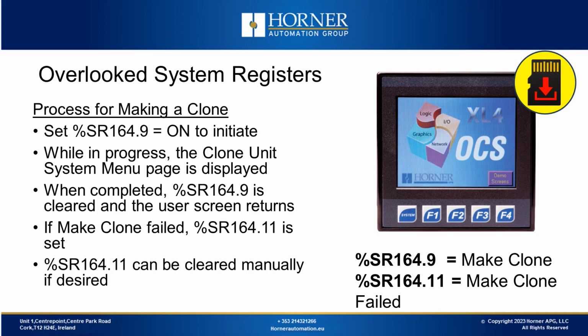We can also monitor another bit, SR164.11, which signals if there's an issue during cloning. If there's a problem, it indicates that the clone didn't execute completely, likely due to a missing memory card in the unit or its removal. This is the process for creating a clone.